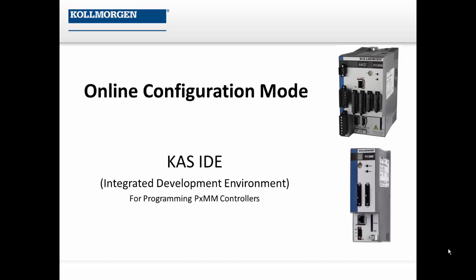In this video of the KAS IDE overview series, I'm going to show you how to turn on the online configuration mode in order to access the AKD drive configuration screens without having a PLC program running. This allows the user to access the auto tuner and service motion screens, which will not work while a program is running because then the EtherCAT controller is in charge of the drive's command position.